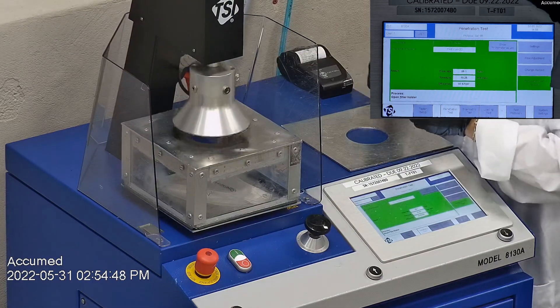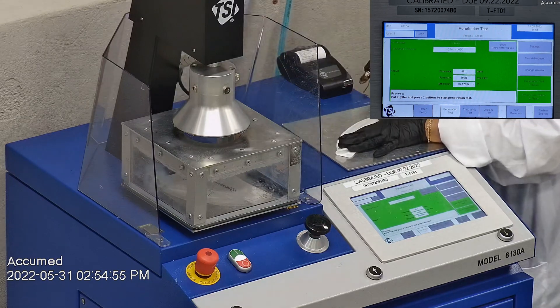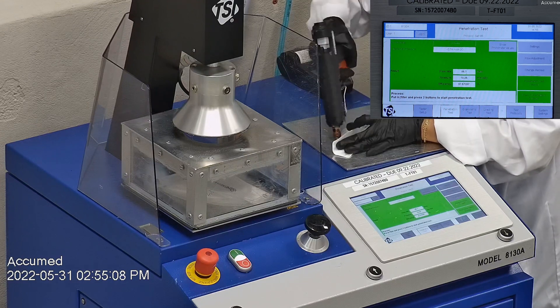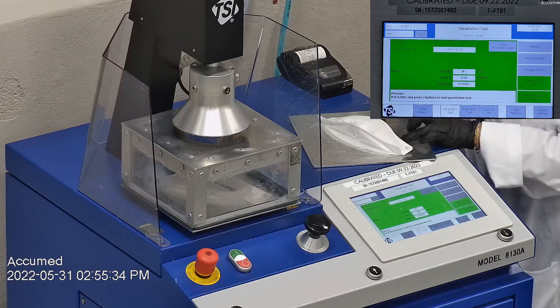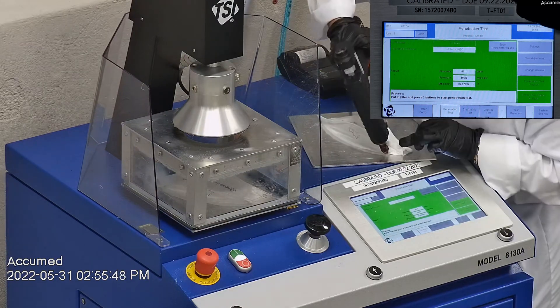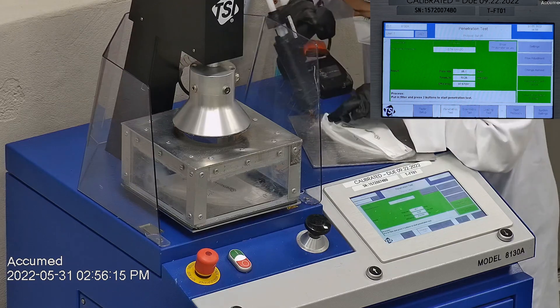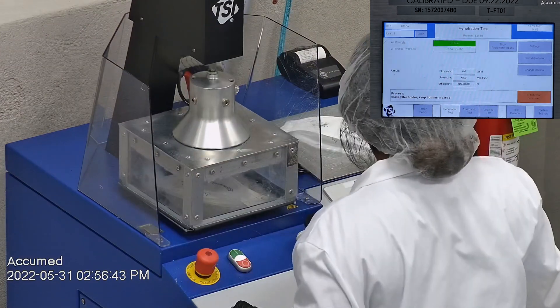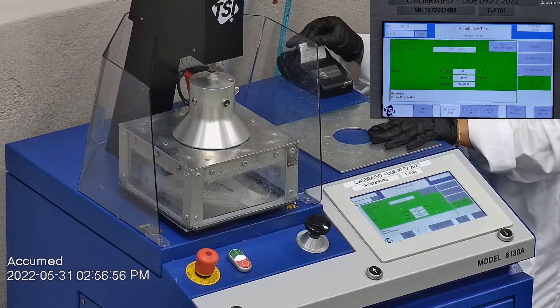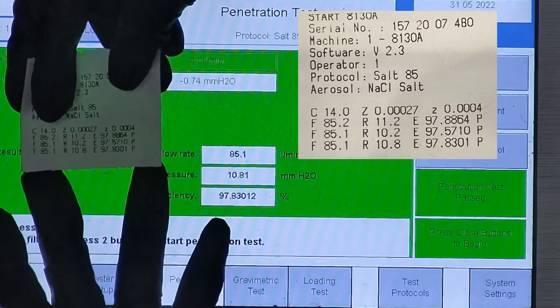The second sample had a filtration percentage of 97.57% and a pressure drop of 10.2 millimeters of water. The last sample's filtration percentage was 97.83% and had a pressure drop of 10.8 millimeters of water.